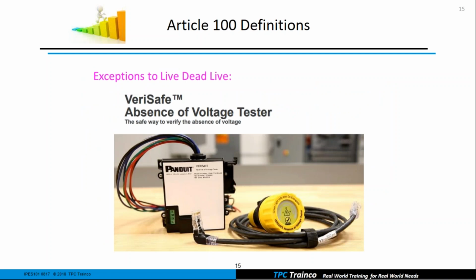Just one manufacturer of these. Almost every company has these now. So this can be permanently mounted inside of a piece of equipment. It verifies it's working properly before it goes ahead and tests phase to phase and phase to ground, and then it verifies it's working properly afterwards. And it gives you an indication. You will get an indication right here when it is safe to work on that piece of equipment.